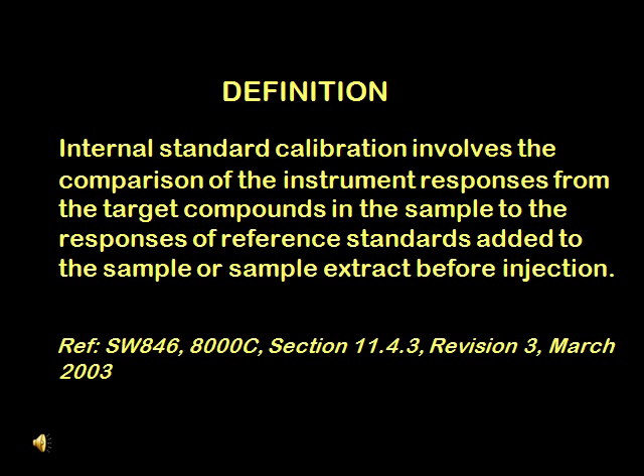In this section, internal standard calibration will be discussed. SW846 Method 8000C defines internal standard calibration as follows: it involves the comparison of the instrument responses from the target compounds in the sample to the responses of reference standards added to the sample or sample extract before injection.